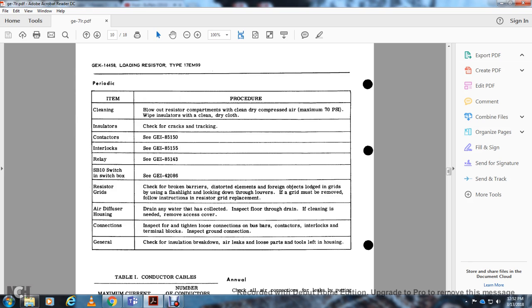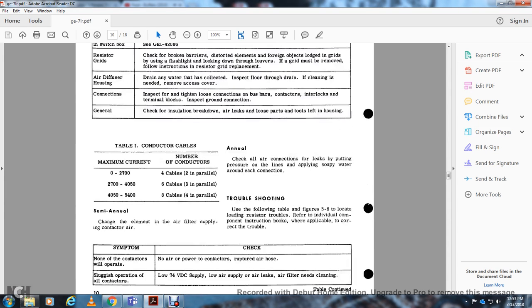If the grid must be removed, follow the instruction: resistor grid replacement. Air diffuser. Drain any water that has collected. Inspect the floor through the drain, and if cleaning is needed, remove the access cover. Connection. Inspect for and tighten loose connections on the bus bar contactors, interlocks and terminal blocks, and inspect ground connection. General. Check for insulation breakdown, air leaks, and loose parts and tools left in the housing.